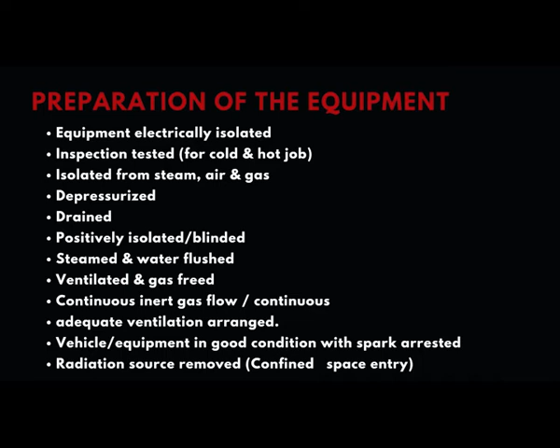This is known as positive isolation. By inserting the blind, you are positively isolating any hydrocarbon or utilities like steam, air, or gas from entering the system. Only after positive isolation can you hand over the equipment for maintenance. Sometimes you may have to steam it and water flush it so that all hydrocarbon vapors are completely evacuated and ventilated, and gas freed so that enough oxygen is available in case someone has to enter the system or perform any hot task.